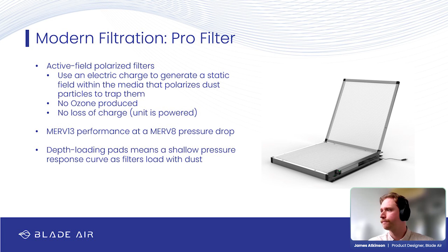Now, I think something to note is that there's also a myriad of other benefits associated with electric charge. So firstly, we actually have VOC reduction. I think it was over 40% reduction in VOCs over a 48-hour period we tested, again, in the distillery district. And that's because a lot of these VOCs are polar molecules. So if you've ever done that science experiment where you rub a glass rod and hold it up to a water stream, and that water stream bends, it's a very similar concept to VOCs in our filters, right? They will be attracted by that electrostatic charge on the filter. They'll be trapped and eventually captured by the filter, and even by some of the dust that's already loaded on the filter, which basically becomes impregnated with these VOCs.